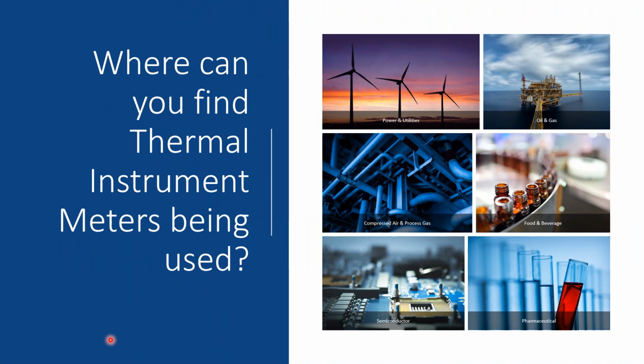Now that you've seen a little bit about some of our designs and where we possibly could fit in, where are we used and where could we be used in your application? Thermal mass is used all over the place. We're used in numerous power generation facilities across the US. We've delivered thousands of units over the years for measuring things like oils, natural gas in boilers, furnaces, kilns, you name it, we've got a unit probably on it. We've done an extreme amount of compressed air, CO2 gas for bottling, clean gases in semiconductor, clean gases in pharmaceutical applications, clean waters for food and beverage. You name it, we've kind of done it over the years.